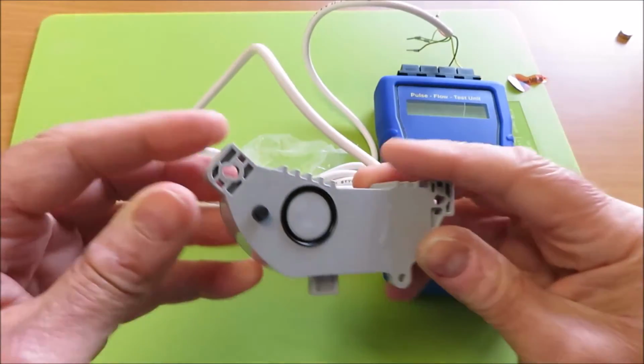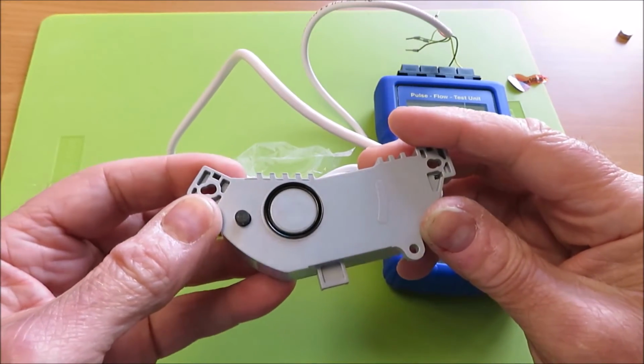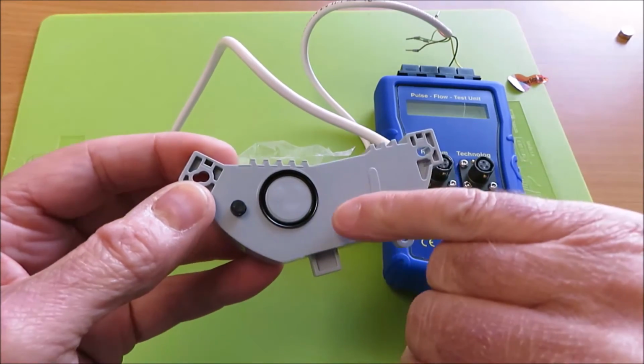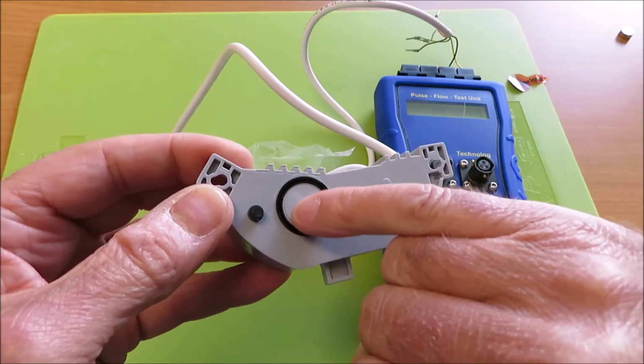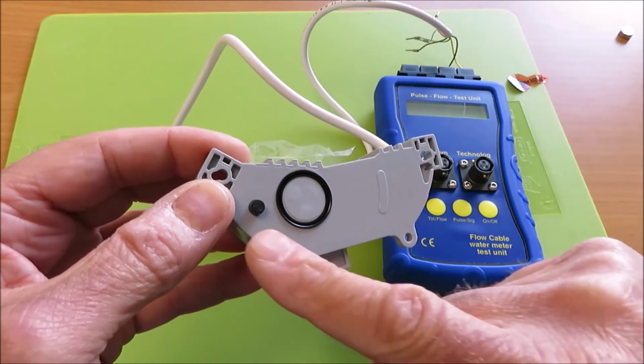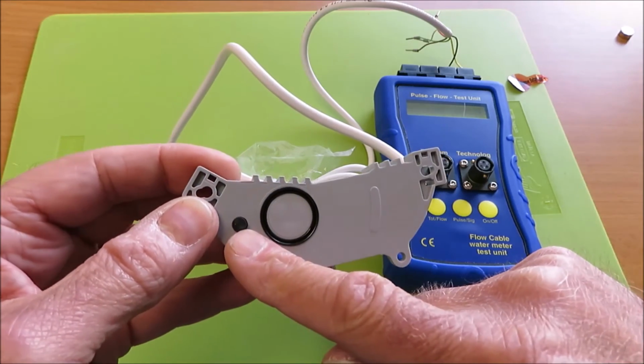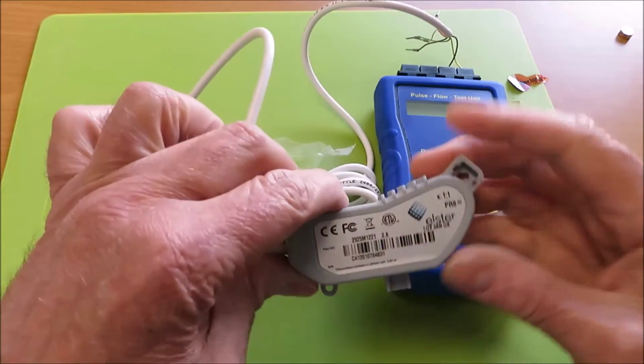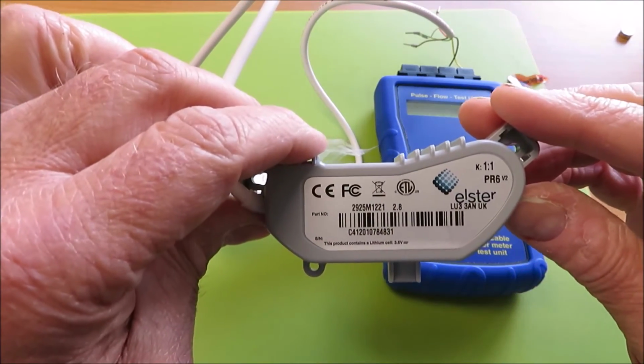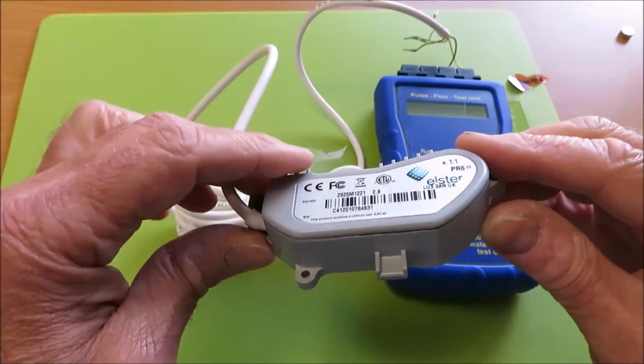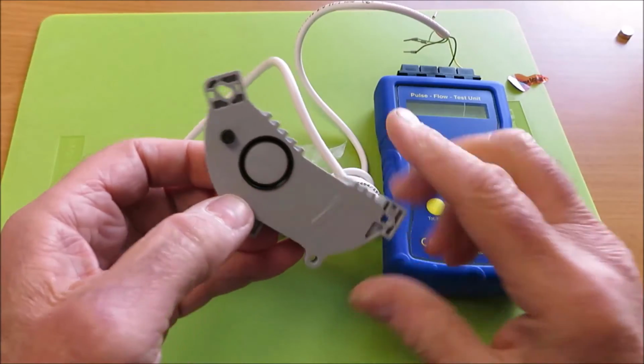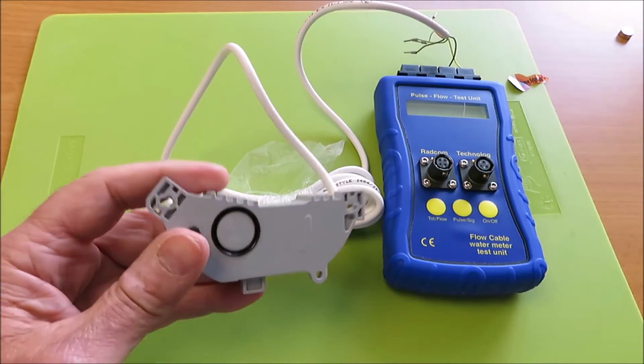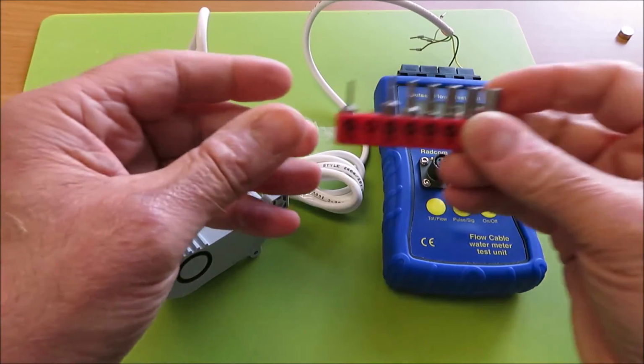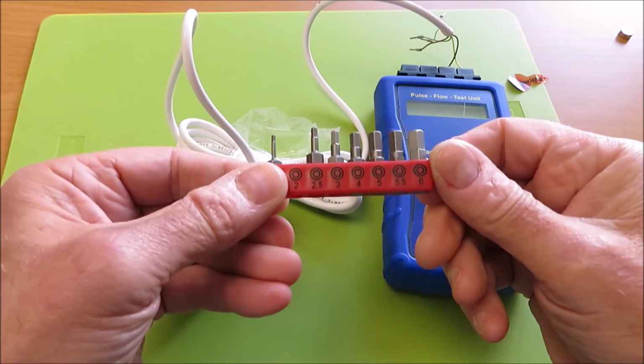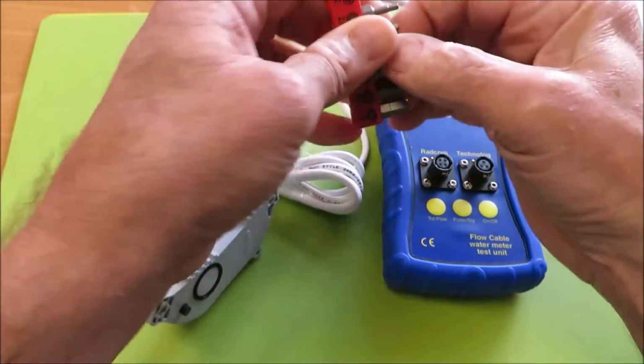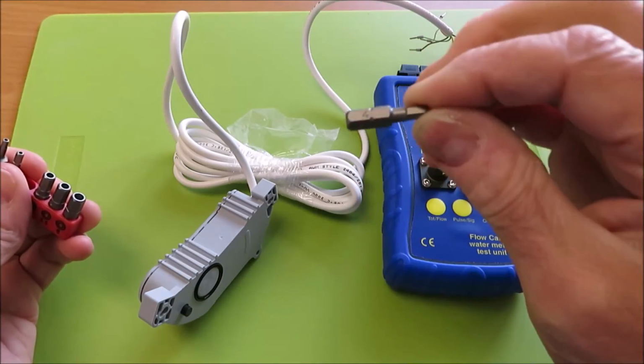And I don't know if you can see, if I get the light just right, can you see there are 3 indentations, just little indentations in the plastic that you can see there. And there's also a little tamper switch which also appears to switch these units on and off as well. And as I say, this is the PR6 unit that we're just going to check that is working here. So I'll turn it over again. I've removed the protective strip there, and actually all you need to test the PR6 is very simply a piece of metal, and I tend to use a screwdriver bit. I just take the screwdriver bit out of the unit. You can see it's just a simple screwdriver bit.